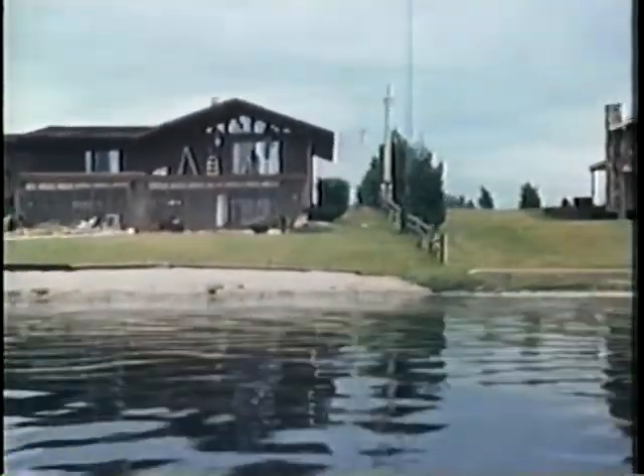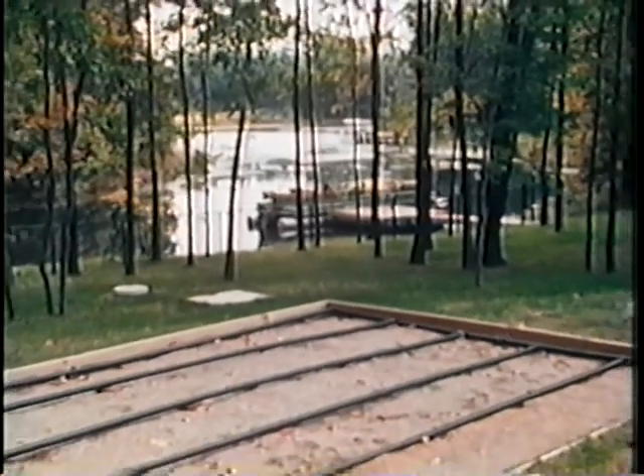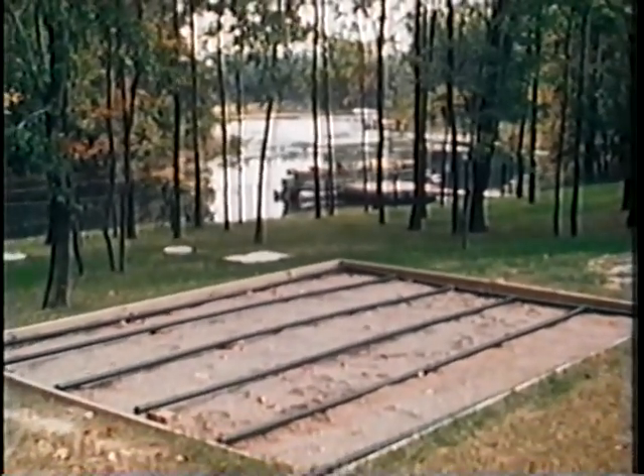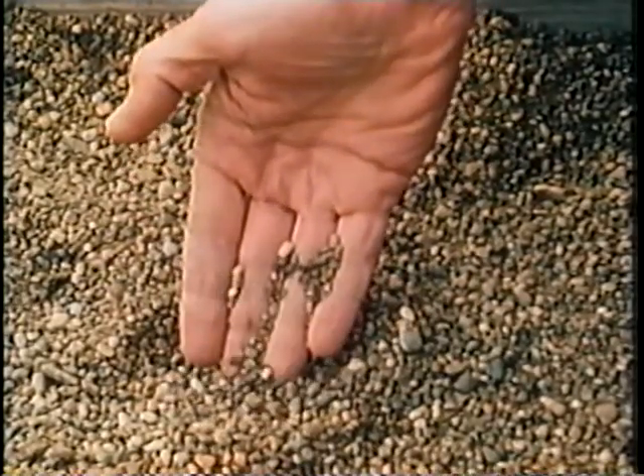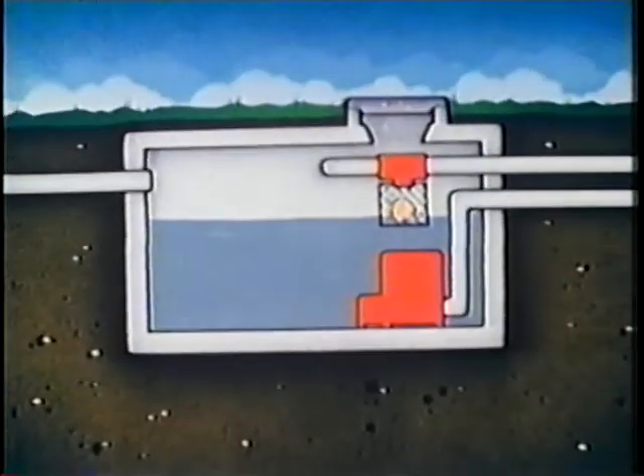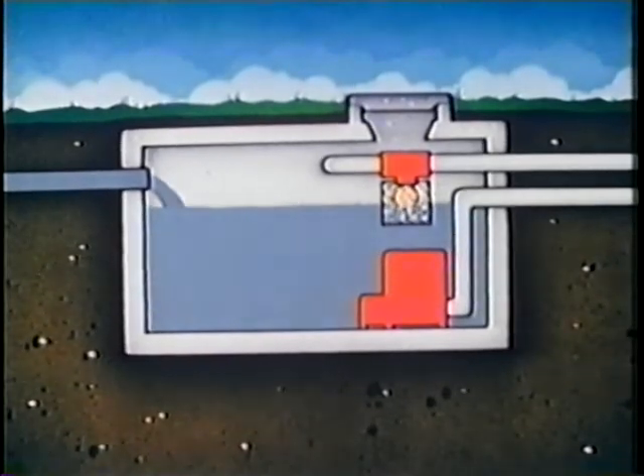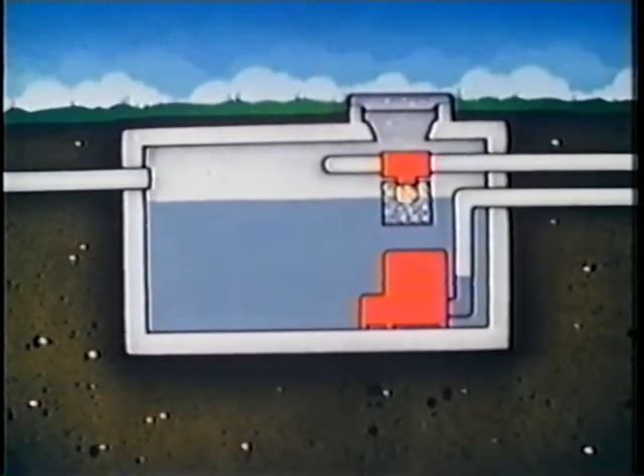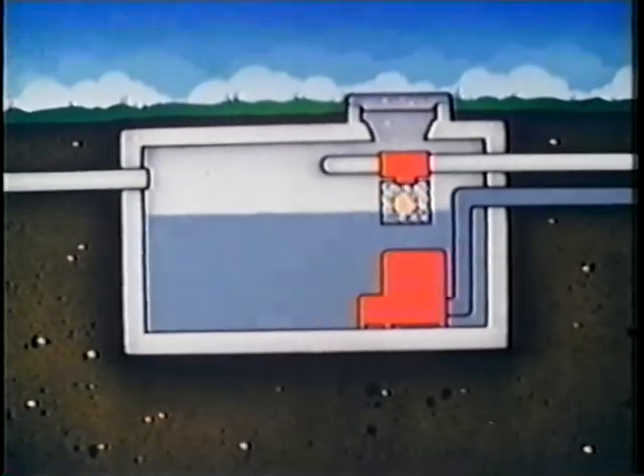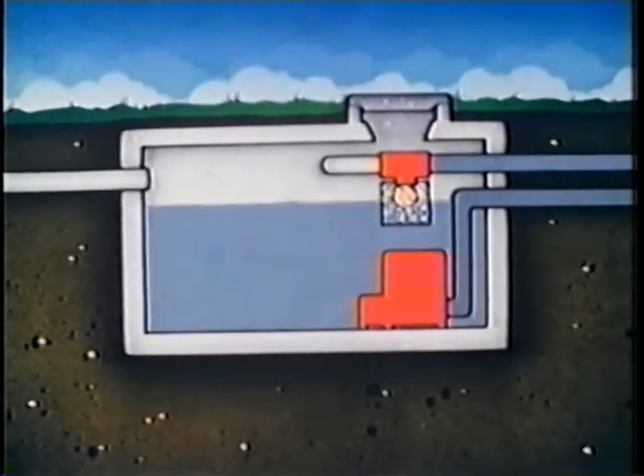Houses on East Fork Lake caused concern for the city of Olney in southern Illinois. The lake serves as a reservoir for the city's water supply. To prevent degradation of water quality, lakeside homes make use of a recirculating sand filter. This system consists of a filter of specially sized sand and a septic tank. A recirculation tank in between accepts effluent from the septic tank and also a portion of the sand-filtered effluent. A time clock determines when the mixture is pumped to the filter surface.